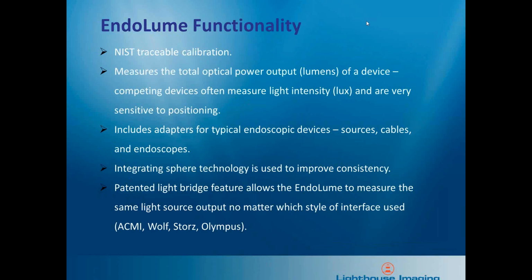As far as the function of the EndoLume, it is a NIST traceable calibration. We use NIST traceable standards in our calibration process. We are measuring total optical light power, which is called lumens.